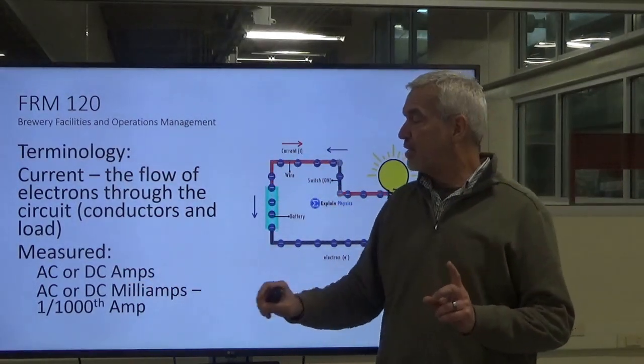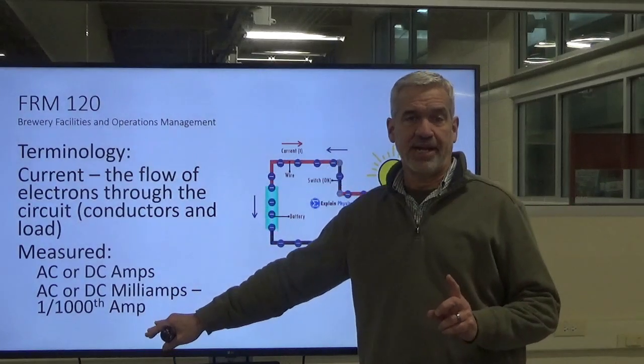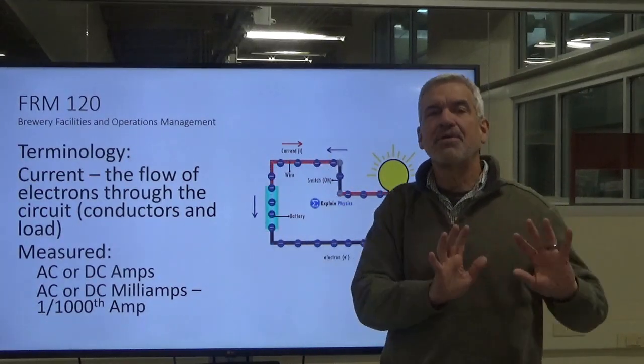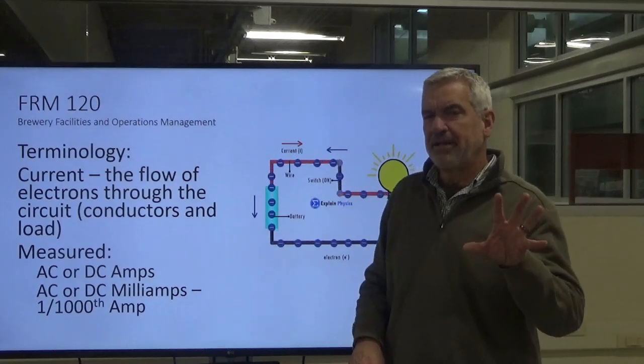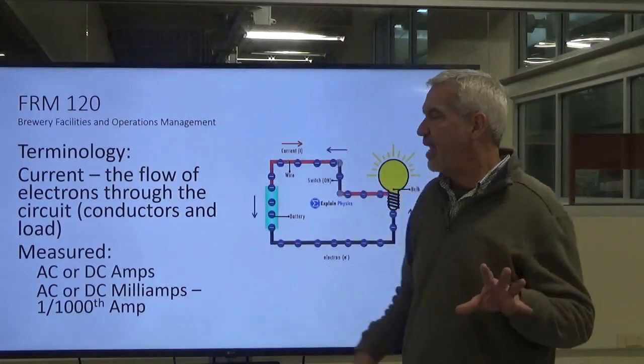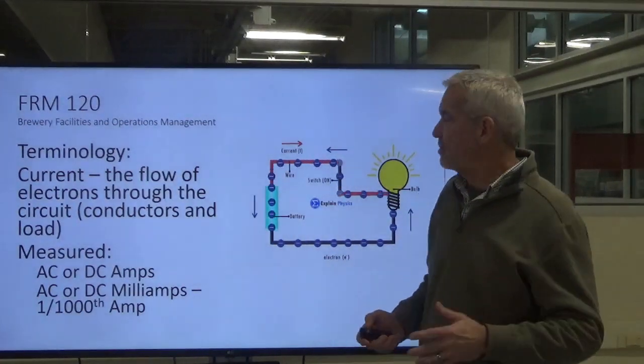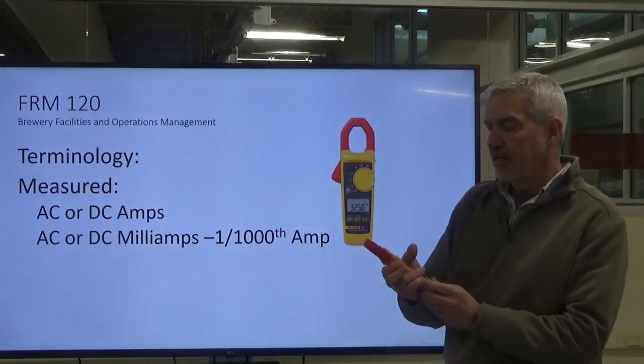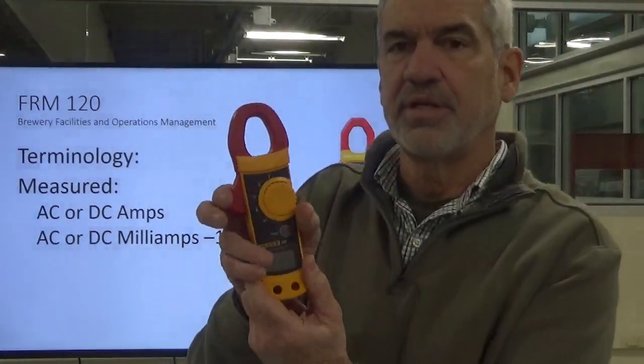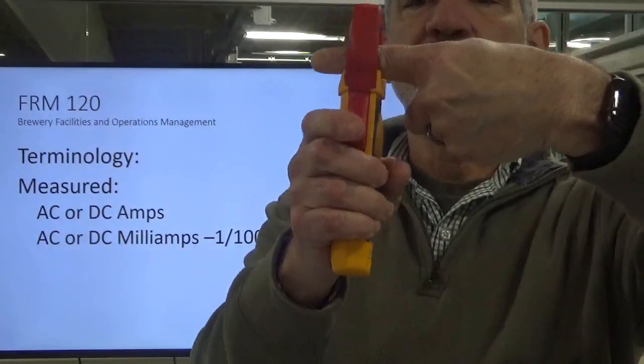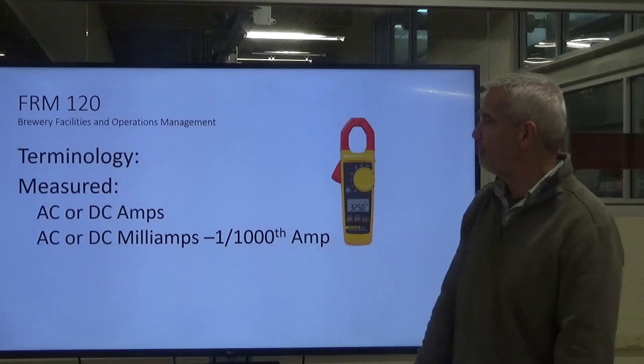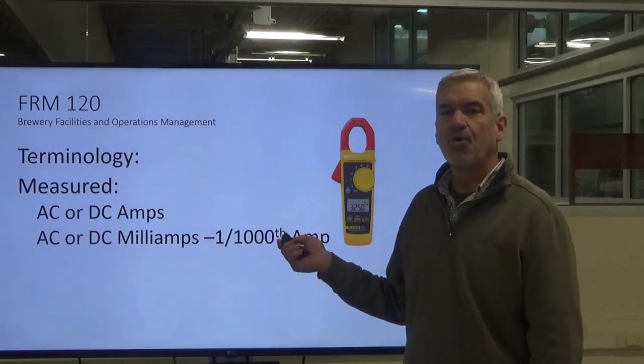We also measure current in milliamps, which is a thousandths of an amp. We use this a lot in control circuits, particularly a range of 4 to 20 milliamps — and that's way deeper than I want to get into right now; we'll talk about that when we get into controls. But just know that current is also measured in milliamps. And we typically use an amp clamp — this is an amp clamp, also a Fluke. It opens up so that you can clamp it onto a wire, and you'll measure the current going through that wire.